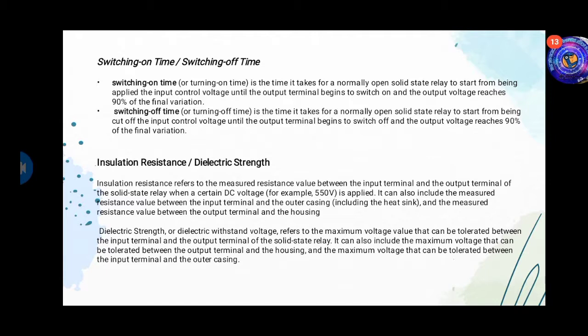Insulation resistance or dielectric strength. Insulation resistance refers to the measured resistance value between the input terminal and the output terminal of the solid state relay when a certain DC voltage, for example 550 volts, is applied. It can also include the measured resistance value between the input terminals and the outer chassis, including the heatsink, and the measured resistance value between the output terminal and the housing.